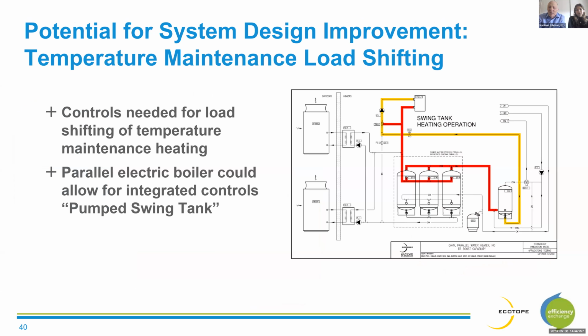We have some design changes that we think could be made to allow us to not only shift the operation of the heat pump, but shift the operation of the temperature maintenance system as well, which we're calling a pumped swing tank. Particularly in new construction at Bayview, we wanted to reuse as much of the existing equipment as possible, so we probably wouldn't use this at a Bayview type retrofit, but for new construction, we think there are design ways to control that swing tank as well.